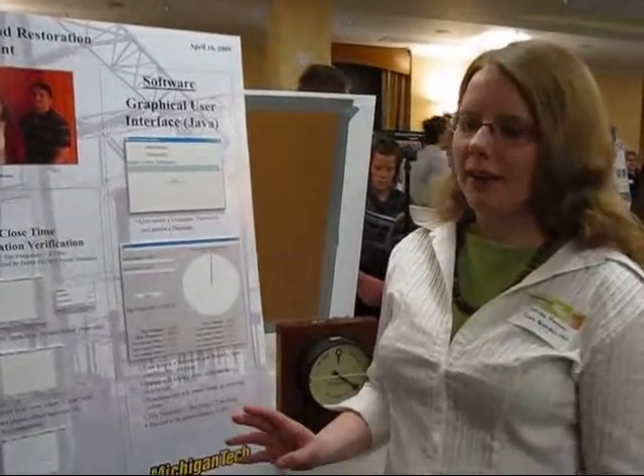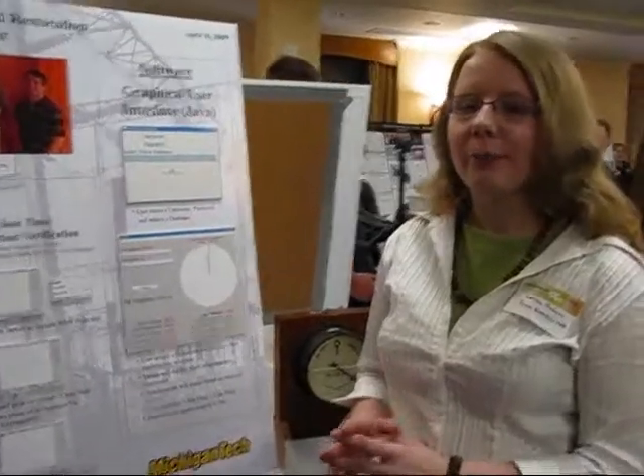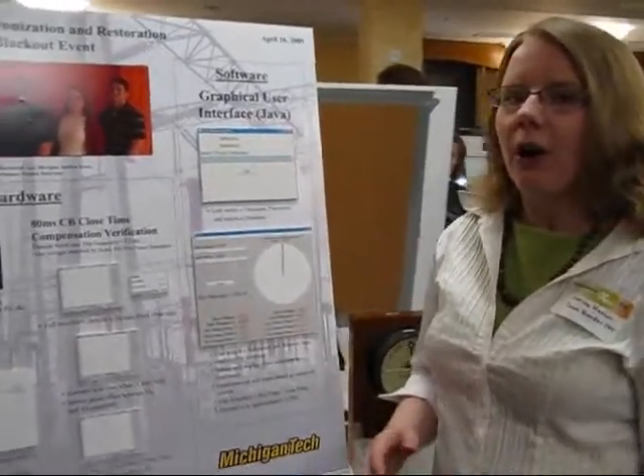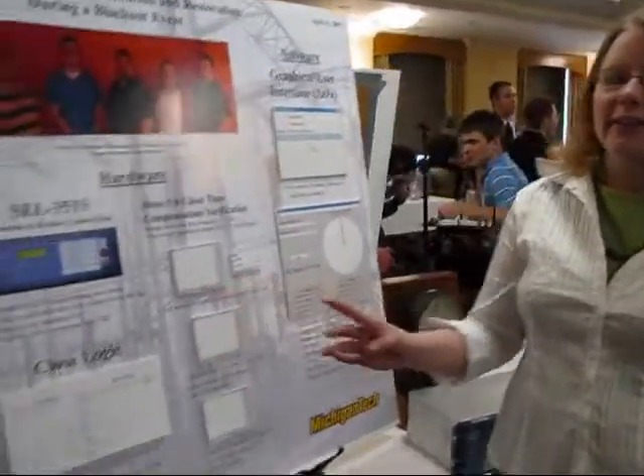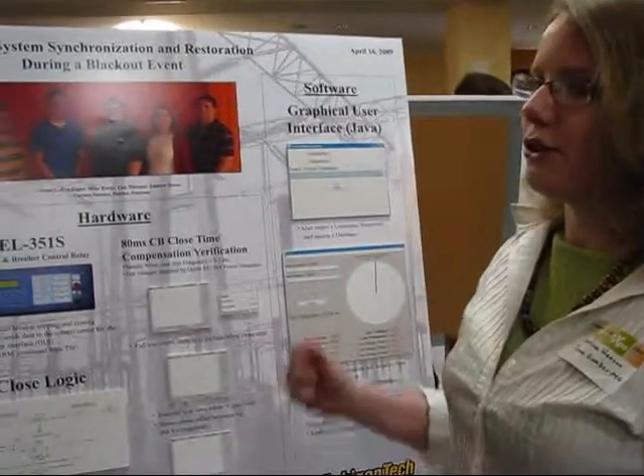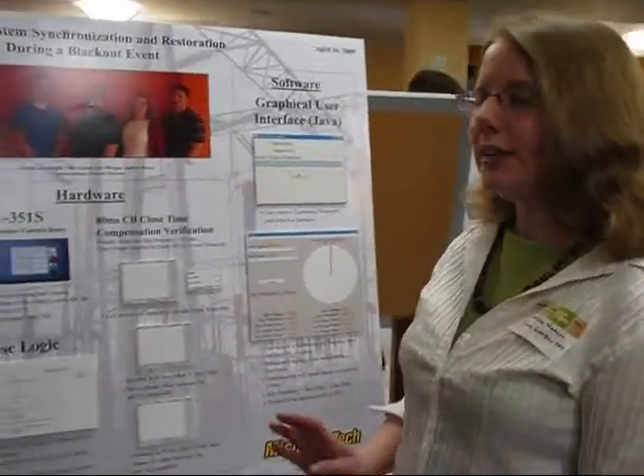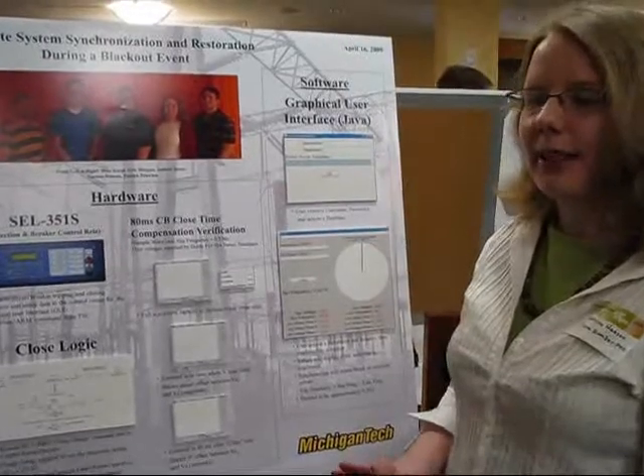What is the power system? When there is a failure or a blackout, it can fall into two different islands of generation and load. If it completely fails, the power system can form two islands, but each island has its own voltage magnitude, voltage angle, and slip frequency. In order to restore the entire system, you have to connect them and tie them together, but if you do it randomly there will be a jolt and damage, so you have to synchronize both values to ensure minimal damage.